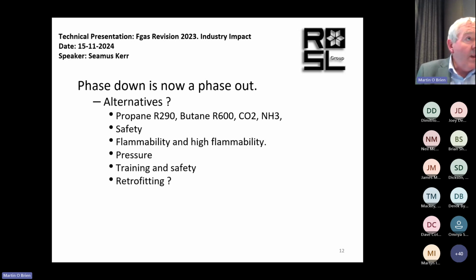We also have ethane. For some of the very low temperature refrigerants like R23 and R508, the only alternative is something like ethane, or a very flammable mix. Ethane is not just flammable, it's explosive. So it's quite different — we're getting into a new side of refrigeration.